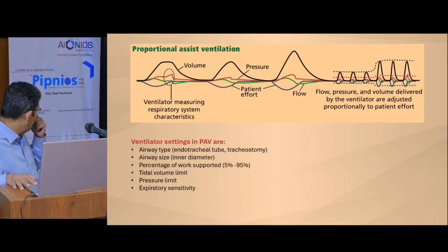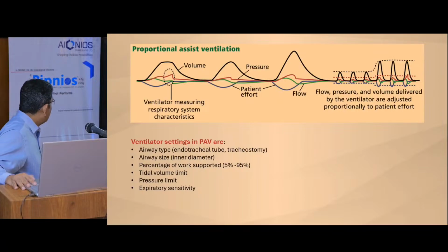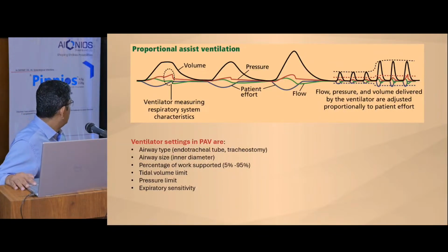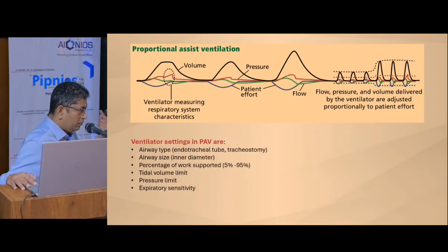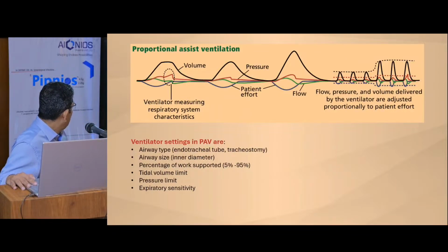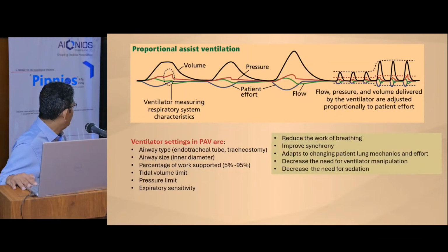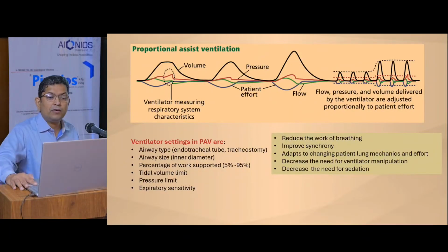So the settings in PAV are the airway type, whether it's an ET tube or a tracheostomy, the inner diameter, the size of the tube, and the percentage of work supported, which can be somewhere from 25 to 95 or 100. Then the tidal volume limit, pressure limit, and expiratory sensitivity. That's all you put. It does reduce the work of breathing.